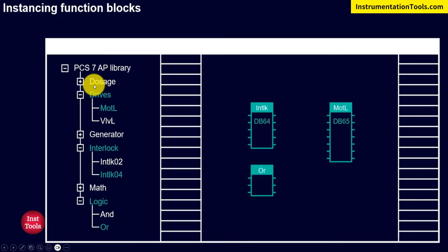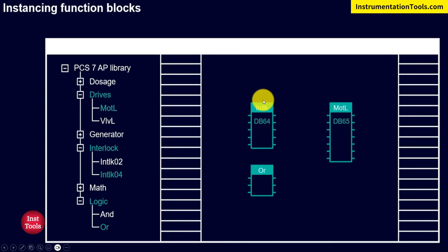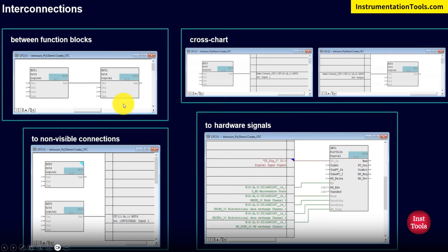In the Catalog, the PCS7 APL library has different classes where FB blocks are already configured. These are type blocks. We instantiate them by dragging and dropping into the CFC plane area — they are instantiated and automatically allocated with DB memory. Whenever we drag and drop an FB, it is considered an instance and is automatically assigned a DB or memory area.